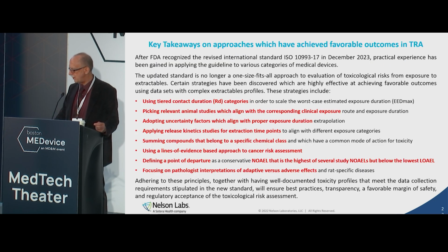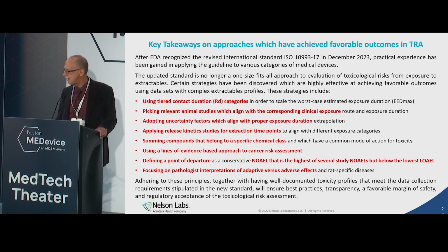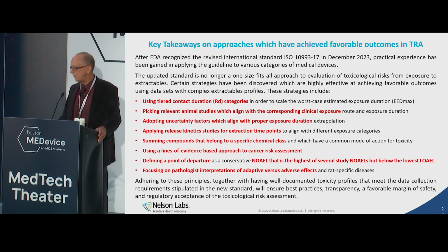Okay, so the key takeaways ending this presentation: after FDA recognized this revised international standard in December, we've gained a lot of practical experience applying it to various categories of medical devices. The updated standard is no longer one size fits all, just pick a NOAEL and do one calculation. There's a lot of detail that has to be provided. Certain strategies have been discovered that are highly effective at achieving favorable outcomes.